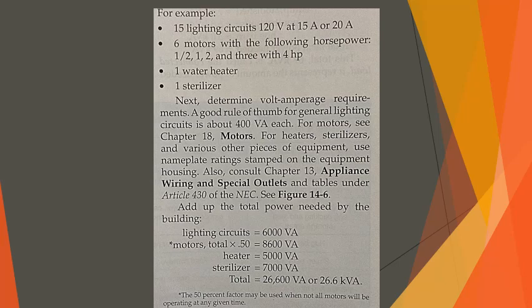Next, determine the volt-amperage requirements. A good rule of thumb for general lighting circuits is about 400 VA each. For motors, see Chapter 18, Motors. For heaters, sterilizers, and various other pieces of equipment, use nameplate ratings stamped on the equipment housing. Also consult Chapter 13, Appliance Wiring and Special Outlets, and tables under Article 430 of the NEC. See Figure 14-6.